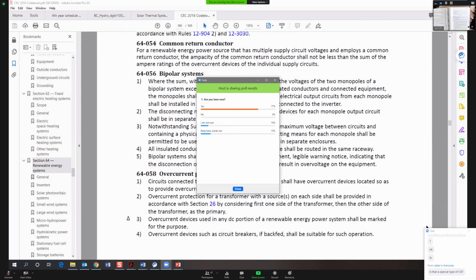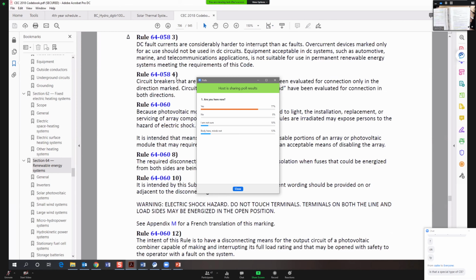If you try to do that, you require a suitable backfeed circuit breaker. So that circuit breaker cannot have a labeling or marking on them telling you this is the line connection, this is the load connection. If you want, we can look at Appendix M. So that's 64-058. Circuit breakers marked with line and load have been evaluated for connection only in the direction marked. And a circuit breaker without a line and load marking is evaluated for connection in both directions. That's what they say is suitable for backfeed. Because if you want to feed the power back into your panel through that circuit breaker, you cannot have the marking on there.